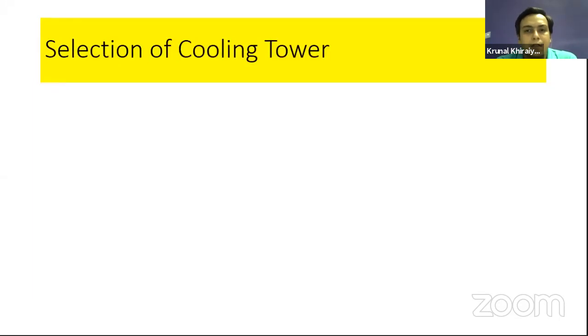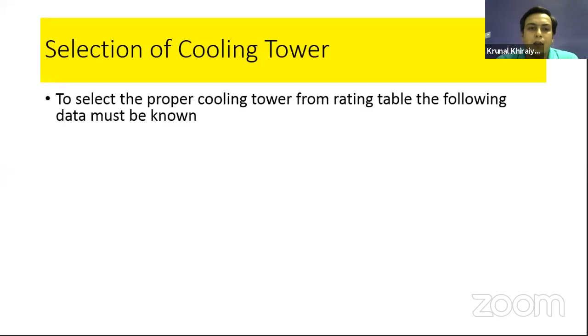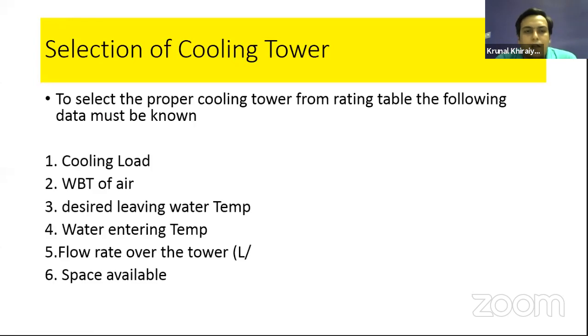Then selection, very important, selection of the cooling tower. To select the proper cooling tower from the rating table, you must know the following data. Actually, most of the time industry people do not go into designing a cooling tower. Instead, they go for selection of a cooling tower. So selection of cooling towers is a very important task. If you select an improper design or improper model of a particular cooling tower, then obviously it cannot be matched with the energy requirement, and if your matching is not there, then obviously you have a loss of efficiency. So the selection of a cooling tower is a very important and critical task.